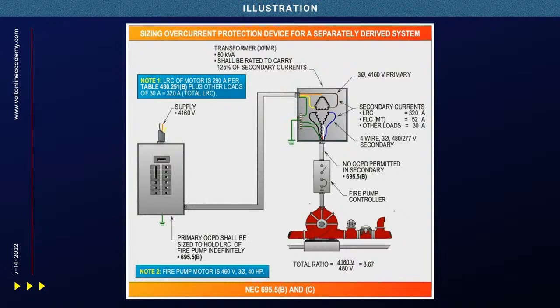Okay. Now, if I look at this, if I take that 4160, divide it by 480, you're going to see you have a ratio for that transformer of 8.67. Okay. And he'll understand it, whoever's on the other end, because I'm going to do the calculation. Now, it's one of my buddies.